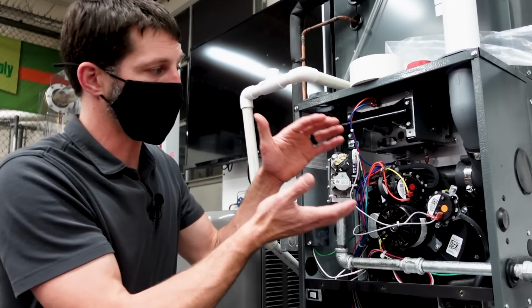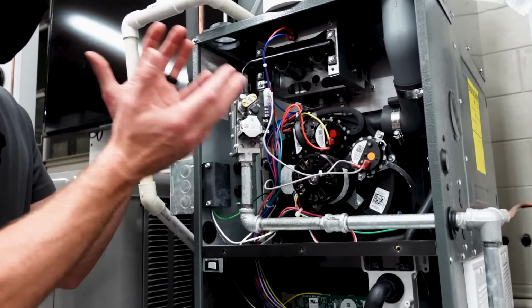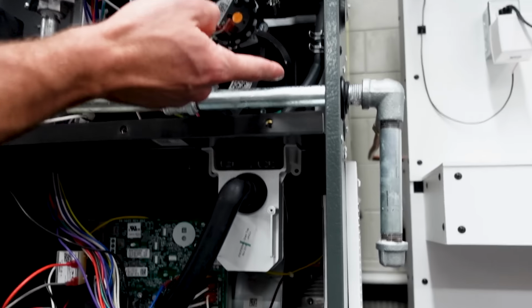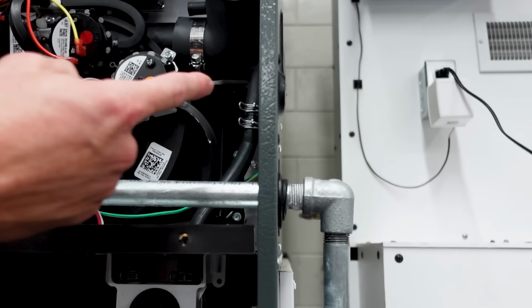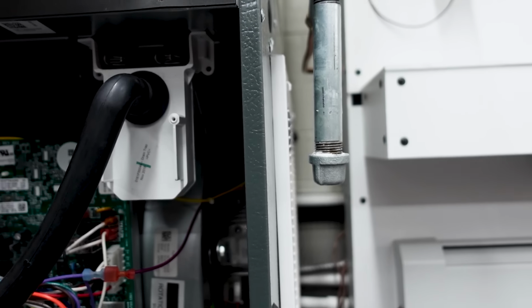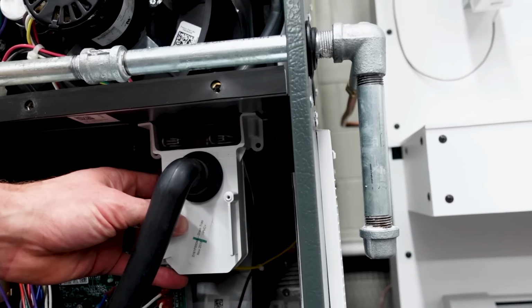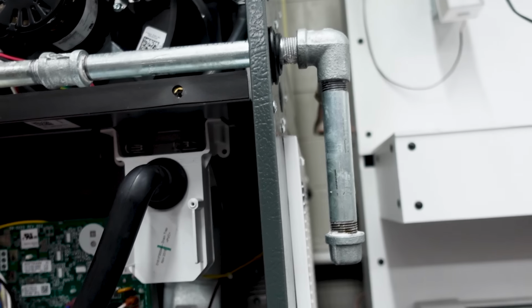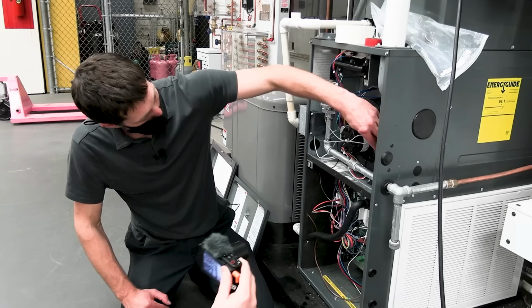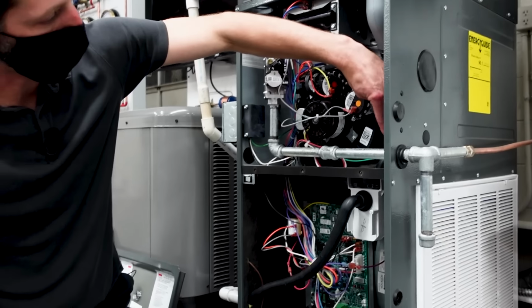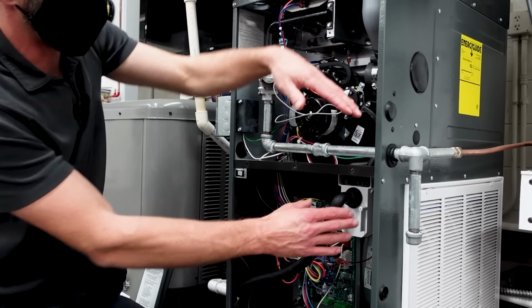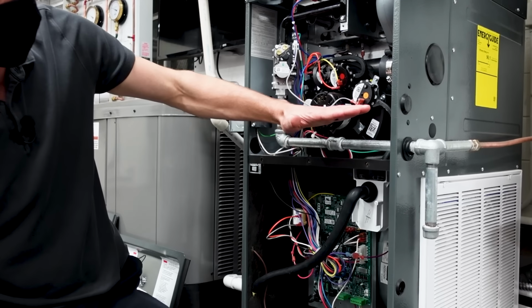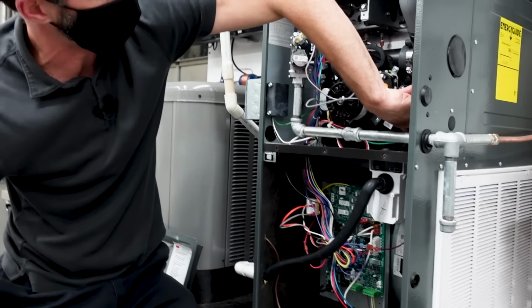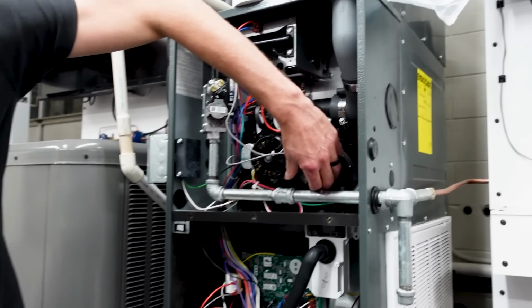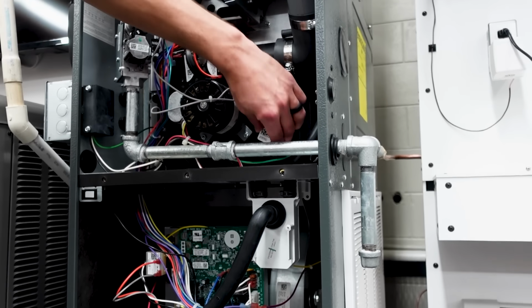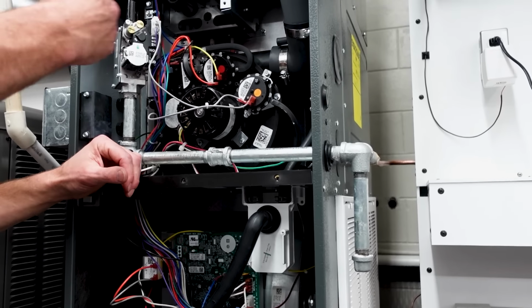It's lowering the temperature of the exhaust so much that the water vapor turns into condensate back here, and it travels through that secondary heat exchanger and drains out right here, and it goes into this trap, this water trap, and then it comes out of the system over here. You have these pressure switches, like this one right here, making sure that this trap is not clogged and that the water is not traveling up higher and higher and higher, because if the water backs up in the collector box, it can get into the inducer motor housing, which is right here, and the blades are going to start hitting the water in there.